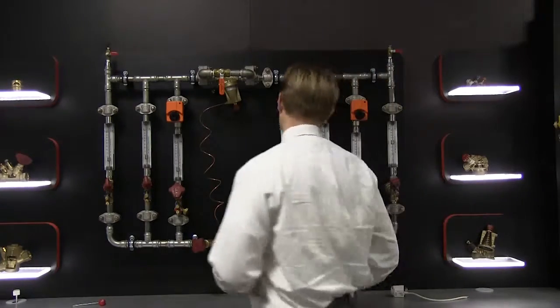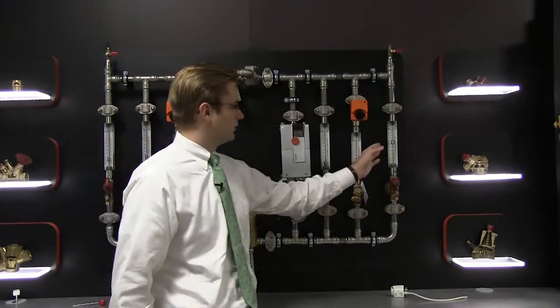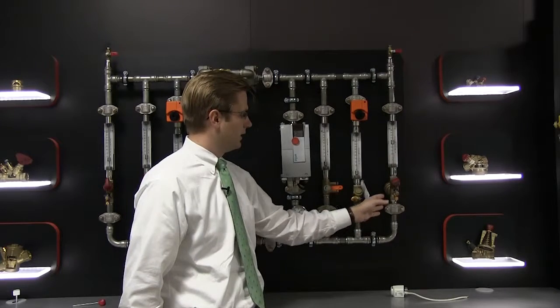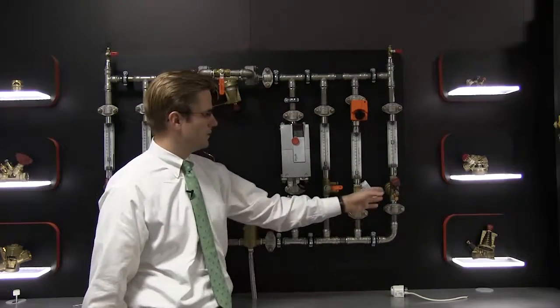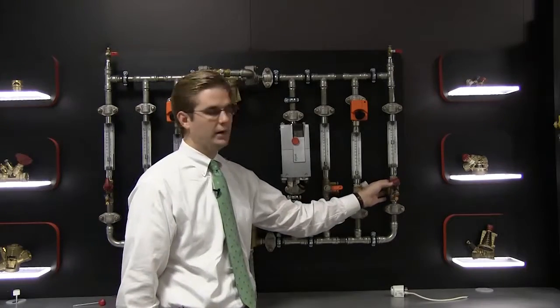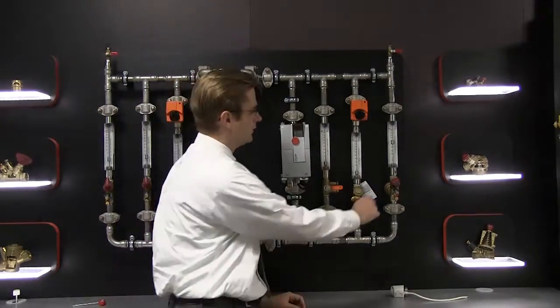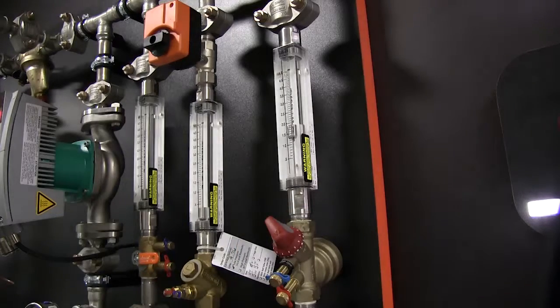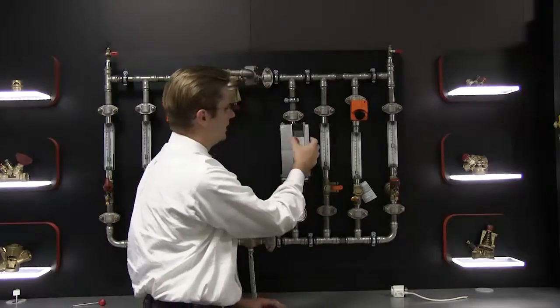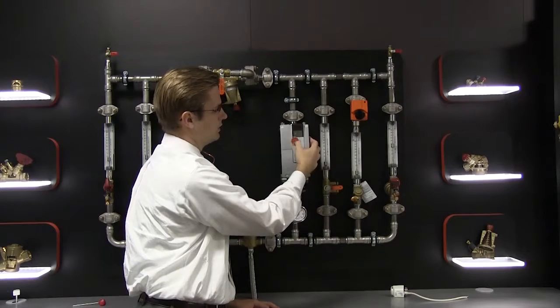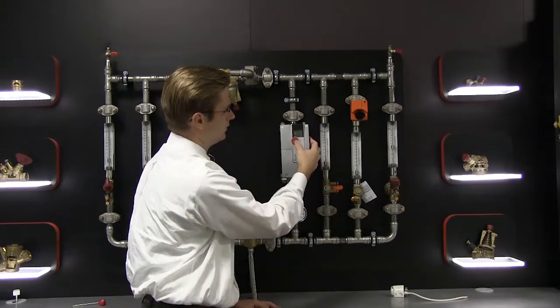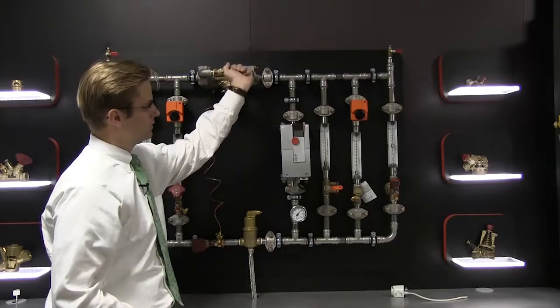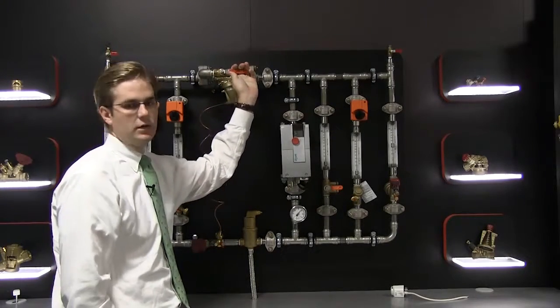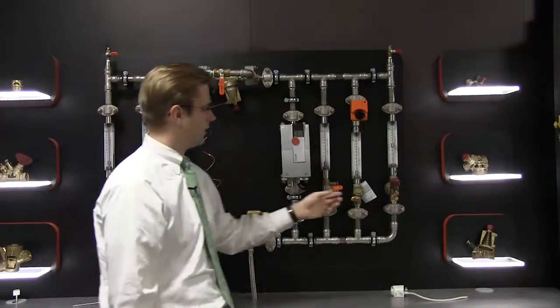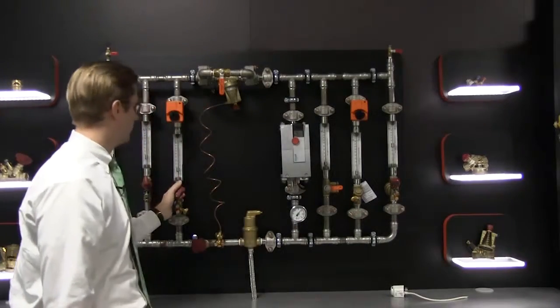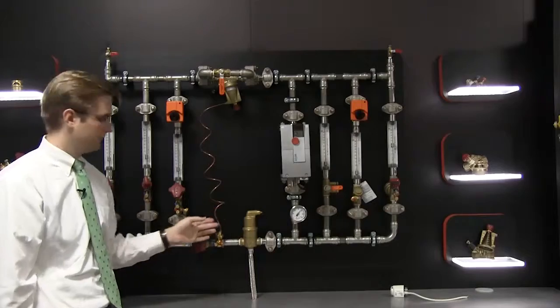The other way to maintain a constant flow rate and achieve pressure independence is by an all-in-one valve, our TBV CMP, which is a pressure independent balancing and control valve. This valve you can set to whatever flow rate you want, and it'll maintain that whether you change the speed of the pump or I change the load to other branches. So this valve combines the manual valve and the differential pressure control valve.